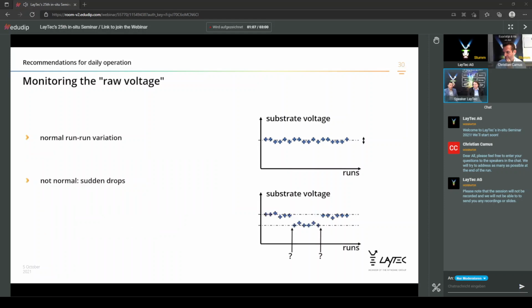What also might happen are sudden drops. Heiko mentioned that. It's very important to check what you have done before the drop happened. It might be that there was reactor maintenance, you cleaned the glove box or the ceiling, or something from the tool was removed and installed again. That indicates that something is misaligned.